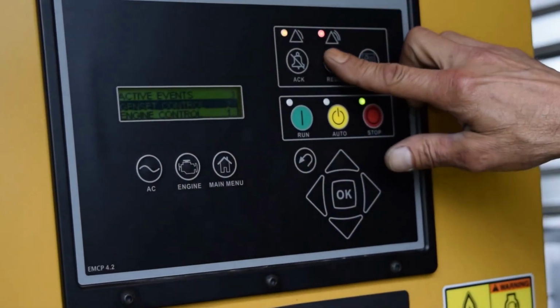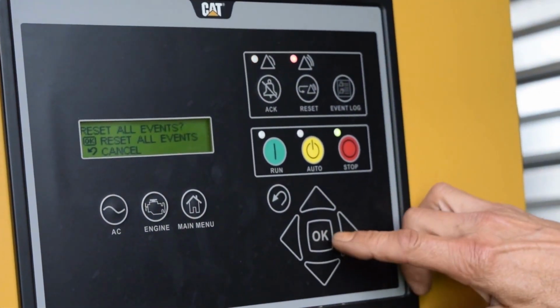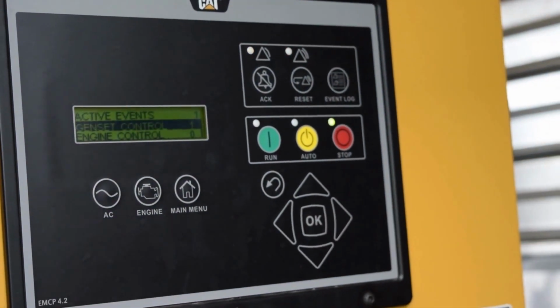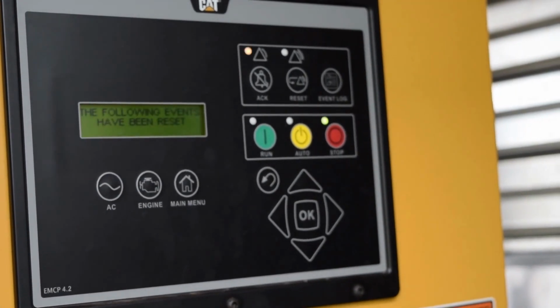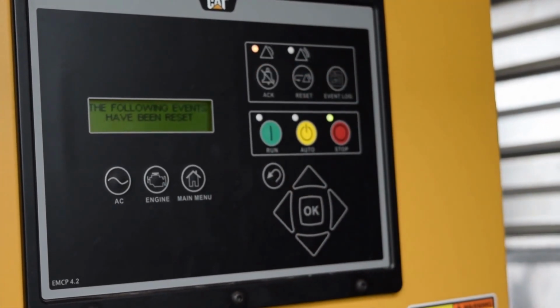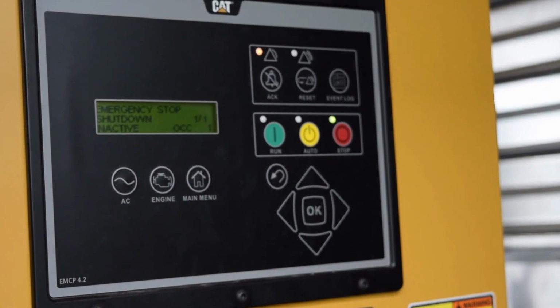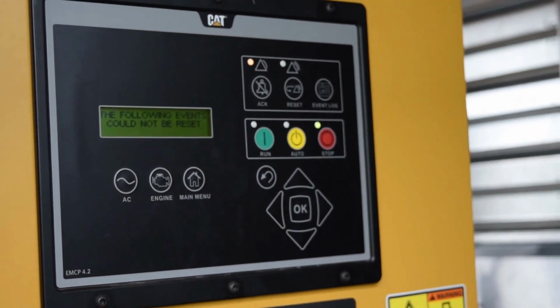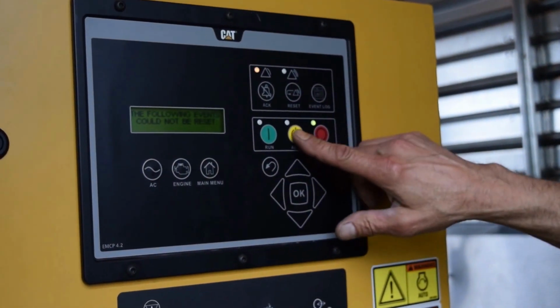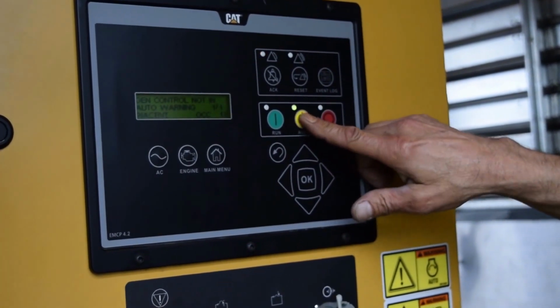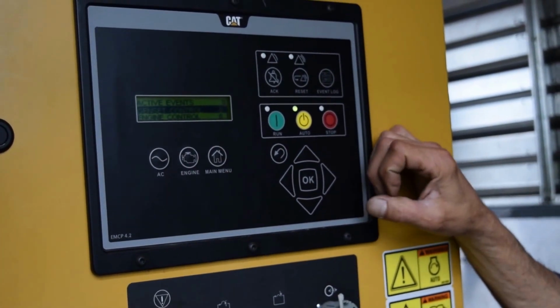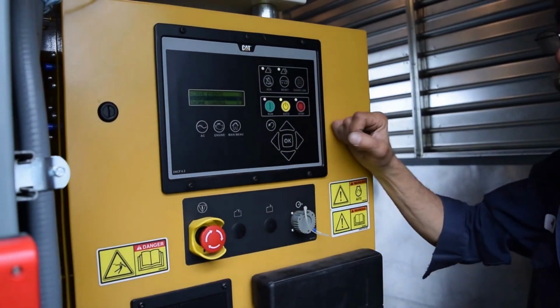So we're in stop, we tell it to reset, we tell it OK, and everything is great. Except we're not back in auto, and we haven't reset our circuit breaker. So with like every job, we would make sure we go back in the auto position and show that to our customer that we have no alarms and that the circuit breaker is now going to be closed.